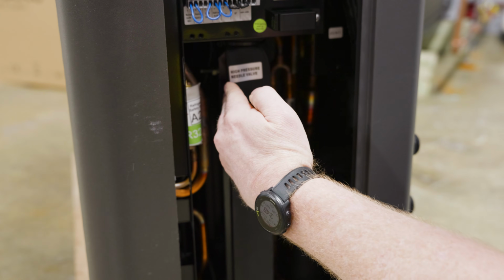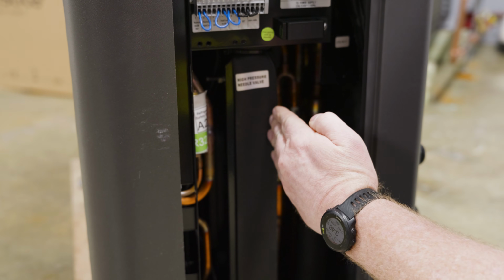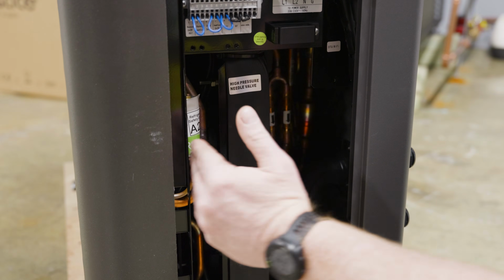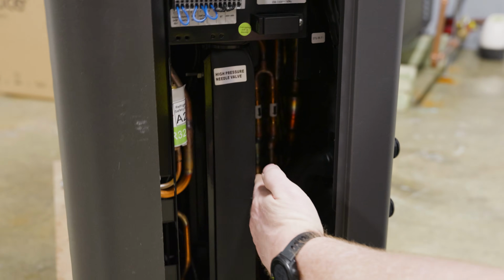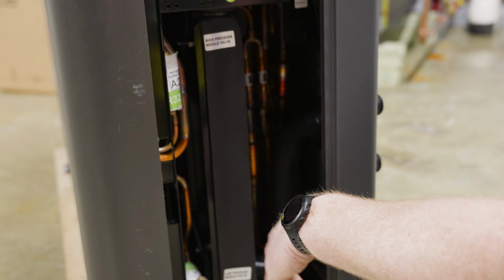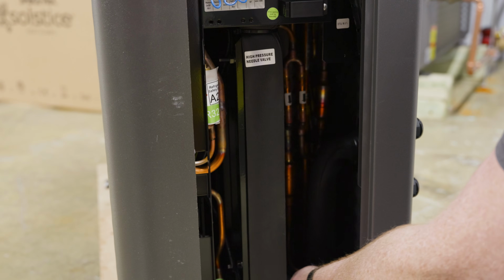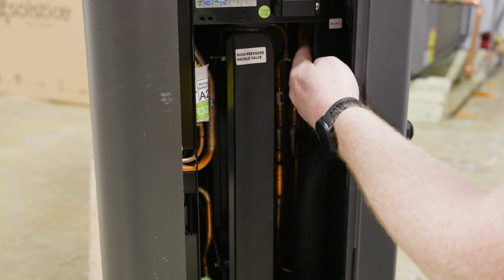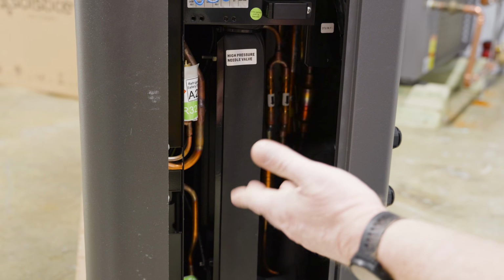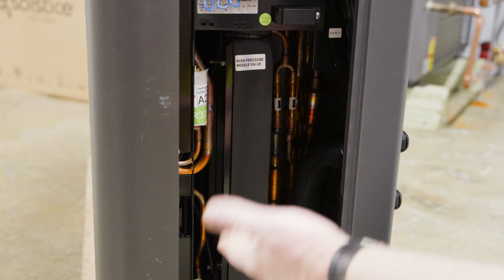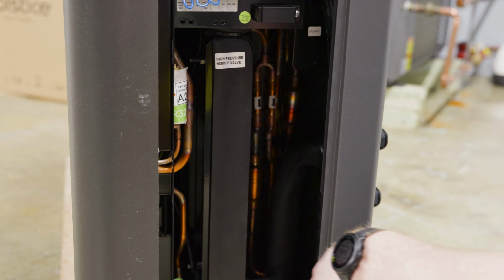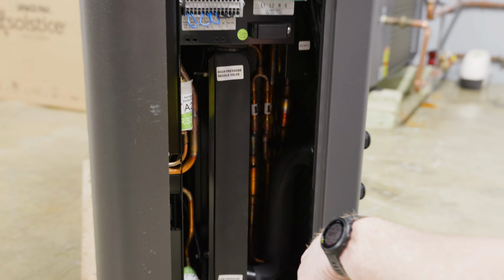Also, on the water side, what we have, this big vessel here in the center, this is actually the refrigerant on one side and water on the other. This is the exchanger. This is where the temperature from the refrigerant gets transferred to that water or water glycol before it either gets heated up or cooled down and then pushed back outside. So here we have a relatively common valve, top and bottom, as far as upon original or initial commissioning, draining any air if this just happens to be the highest part of the system.